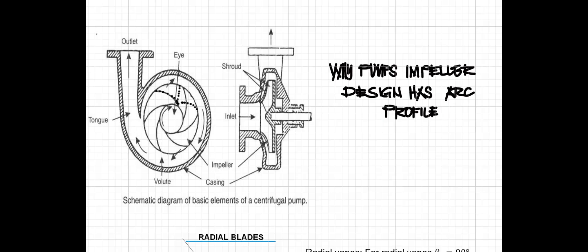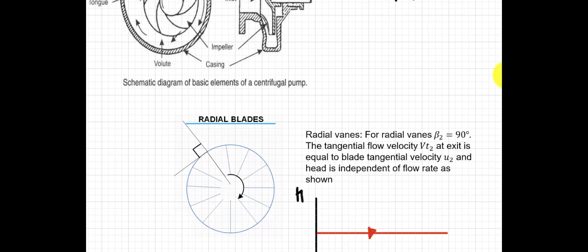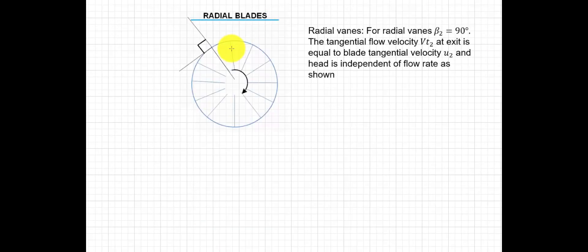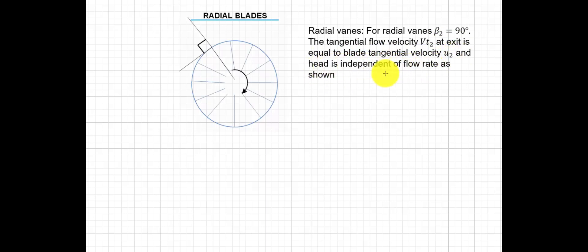Have you ever wondered why the impeller blade design of the pump is in this form? We have different types of blades. For radial blades, the vanes are at 90 degrees, and the intake angle is also 90 degrees. The tangential flow velocity vt2 at the exit is equal to the blade tangential velocity u2, and the head is independent of the flow rate.